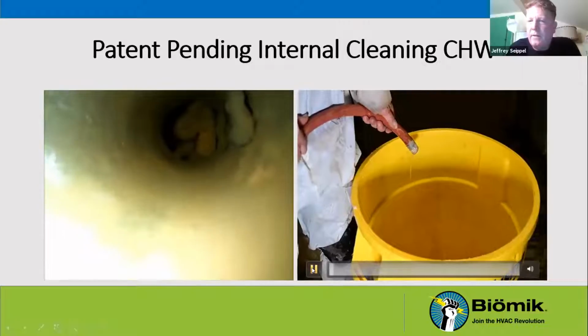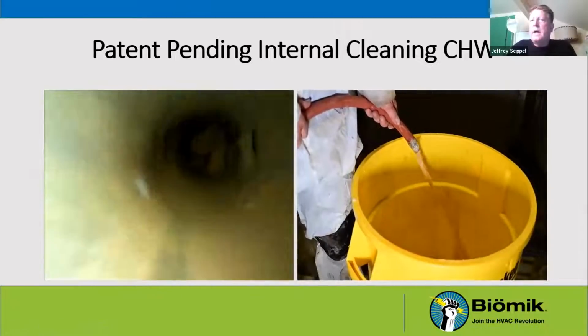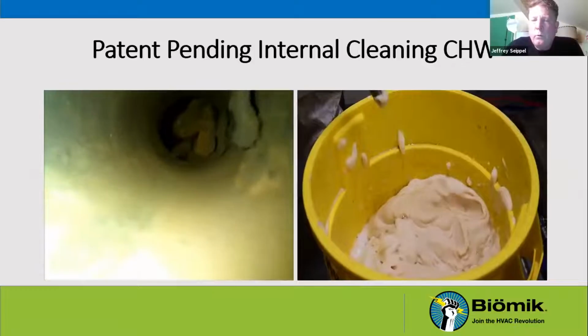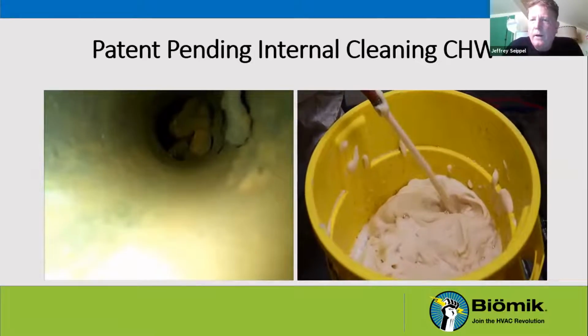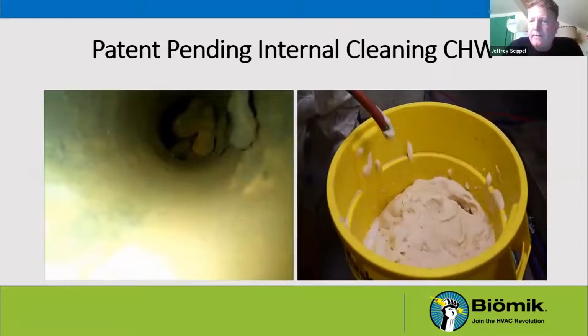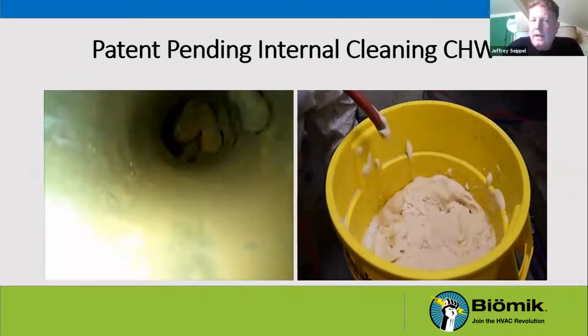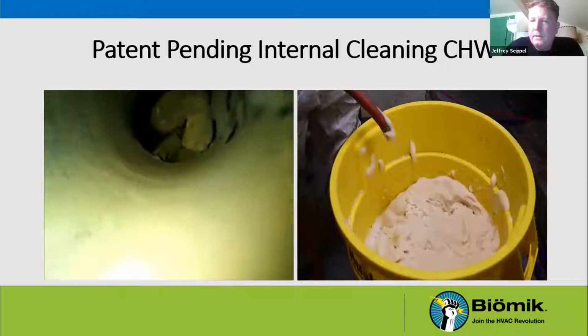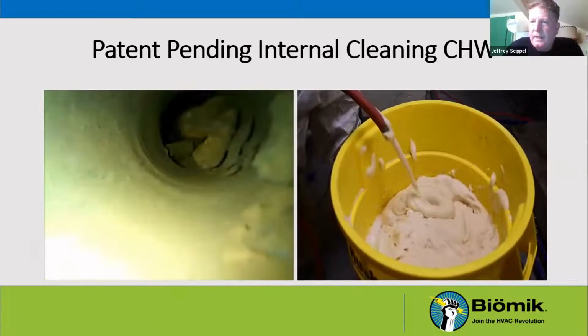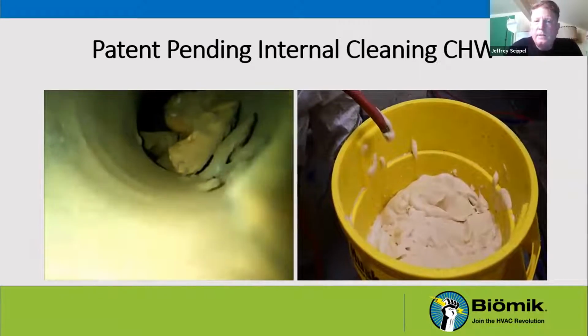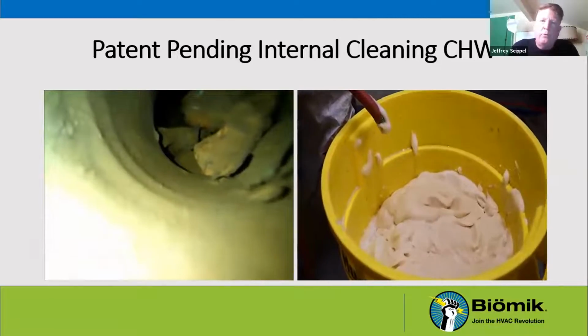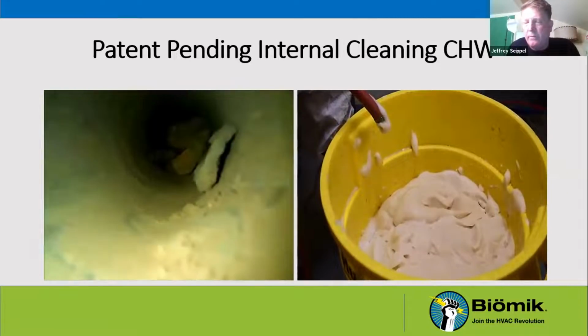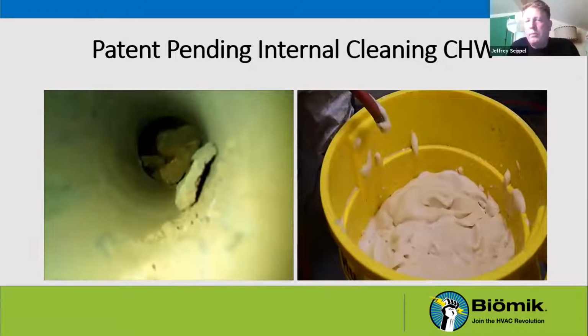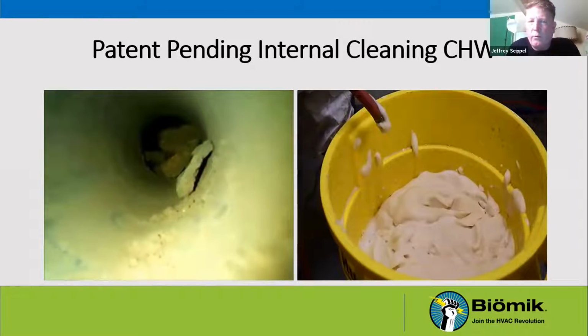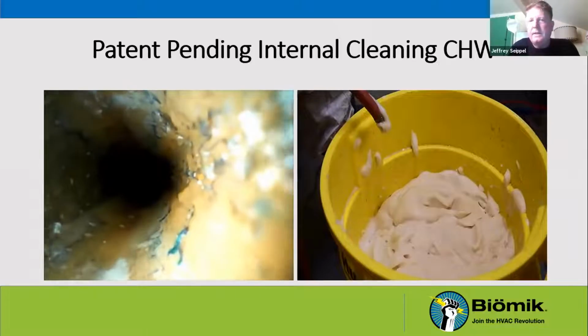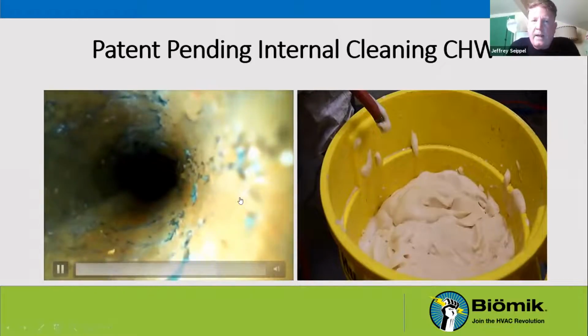The process that we developed is using, again, the probiotics, but we use it with a high density foam that we pump through the coil at 50 gallons a minute. So we're able to treat the biological aspects. And then the big advantage of having the foam is that we can actually pick up and remove very heavy sediment from the coil. So we're improving the thermal transfer of coils both on the air side and on the inside.